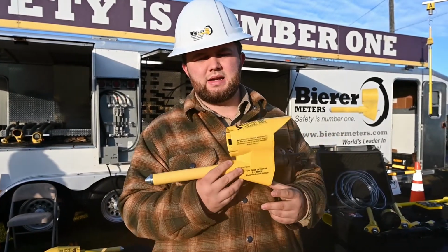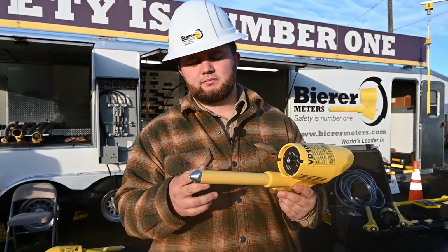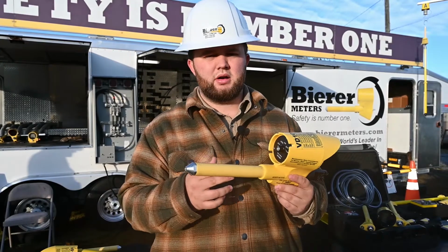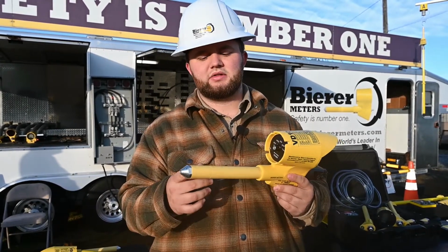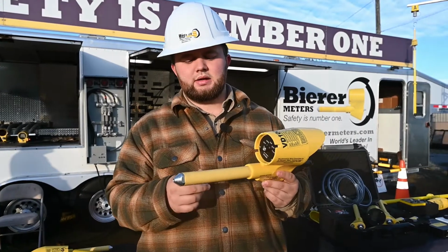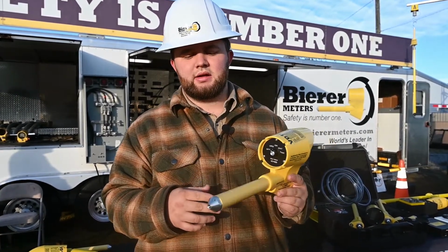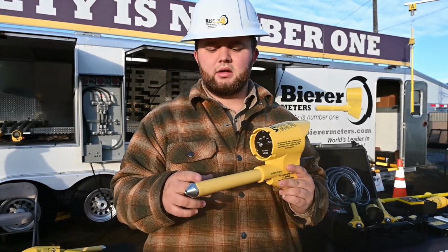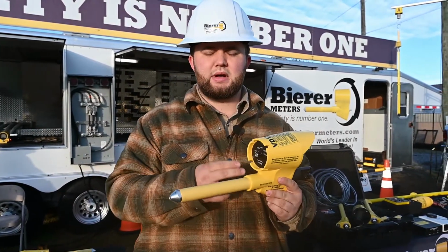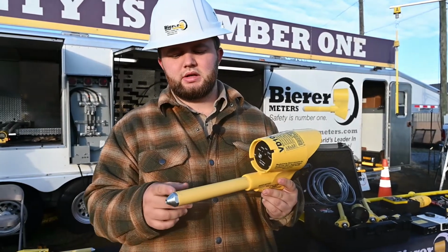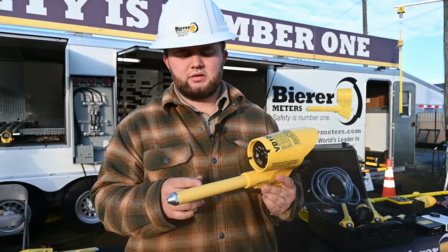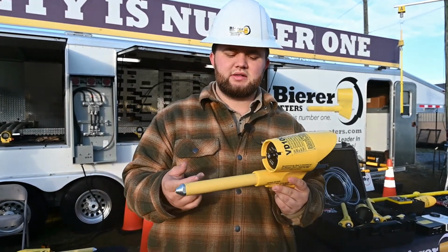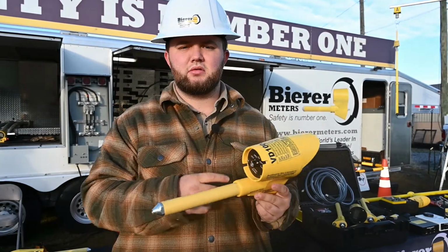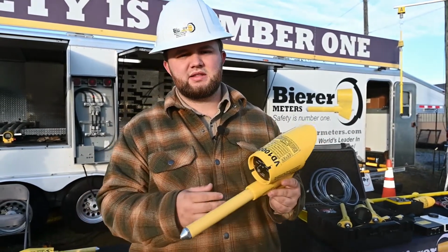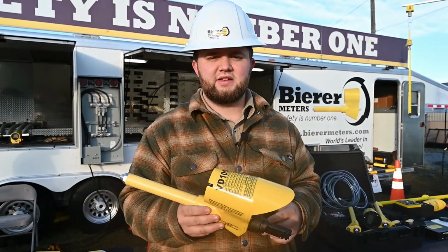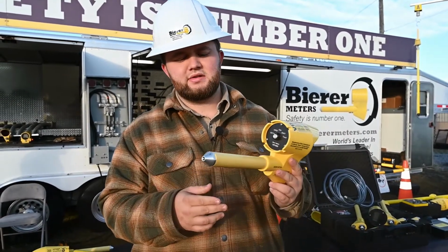That epoxy keeps out any type of outside atmosphere. The outside atmosphere, if you start getting water or dirt, grime inside these tools, what that could cause is a track to those conductive components. So that eliminates any of that risk. So since the tool's sealed off inside, what you then want to worry about is keeping the tool clean externally. You want to keep it clean on the outside of the tool. So if you get any stickers on the outside of the tool, dirt, grime on the probe, what that could cause is a track to those conductive components if you're using the tool improperly. If you're using the tool properly, a lot of times it's not going to matter. But if you start using the tool unsafely or improperly, then that's when you can start seeing some issues.